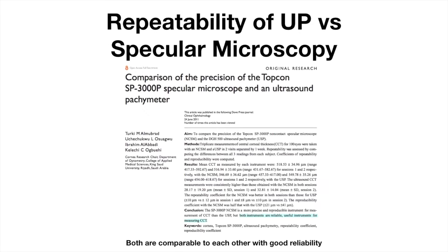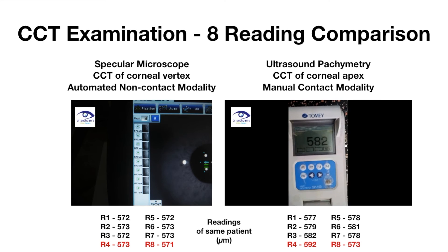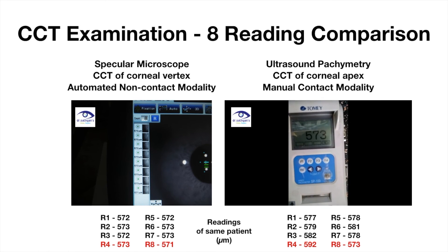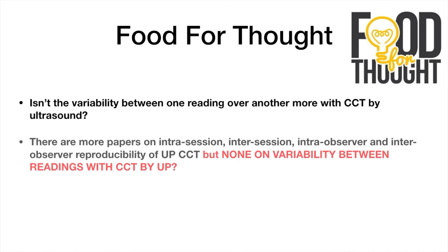The literature showed both ultrasound and specular are equally reliable. But when it came down to variability between consecutive readings, specular had more consistency than ultrasound, which showed a difference of approximately 20 micrometres between its highest and lowest reading. Isn't the variability between one reading over another more with CCT by ultrasound? Has this fallen in our blind spot?